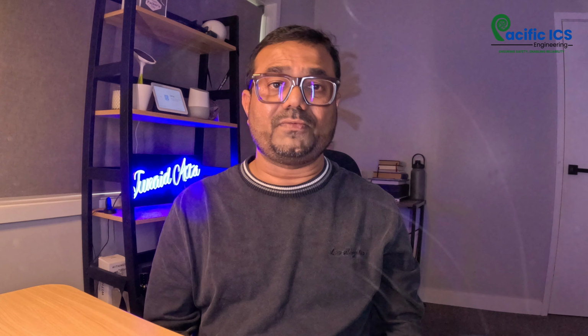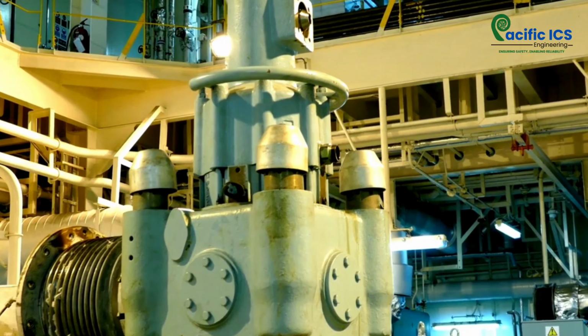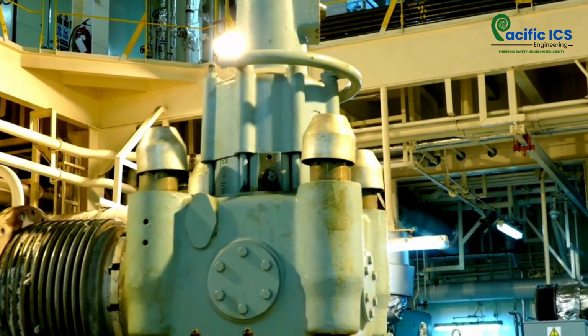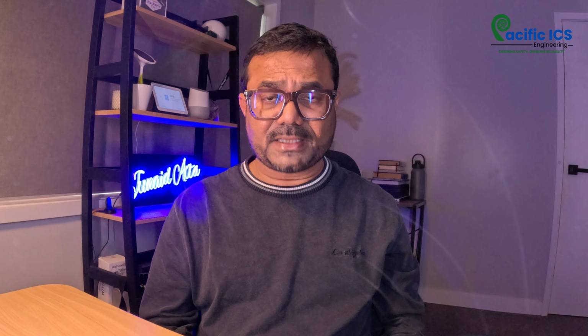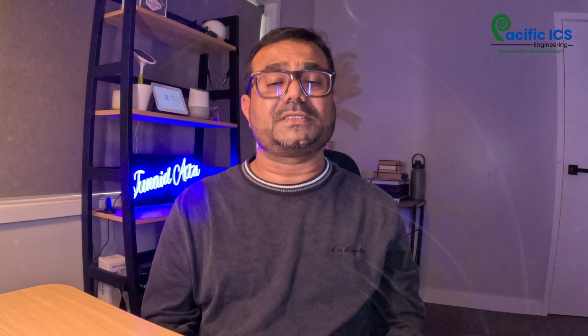Even the most reliable SCEs reach the end of their life. But here's the rule. Never decommission an SCE unless you are absolutely certain it's no longer needed. You will conduct a risk assessment, validate alternative safeguards, and update the safety case accordingly. Let's say the redesign eliminates the need for our pressure-based SIF. Before decommissioning, we must verify a new overpressure protection system is fully functional and independently verified.